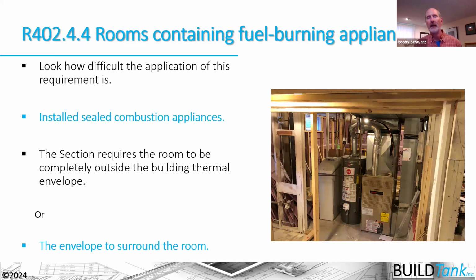So again, if you were going to do it, you'd want to make sure that you get your air barriers up first, and then you cut right size holes through the air barrier to take duct or piping or wiring or other things through the air barrier around the house there. But again, in essence, it's much easier to just design with sealed combustion appliances. And one potential avenue to that is moving to electrified appliances, so that we don't need that combustion air at all there.